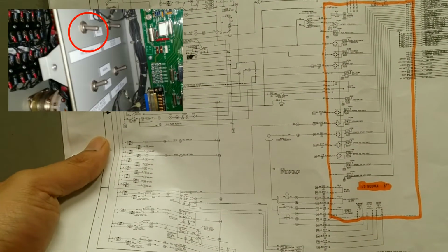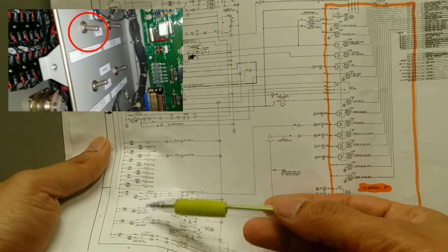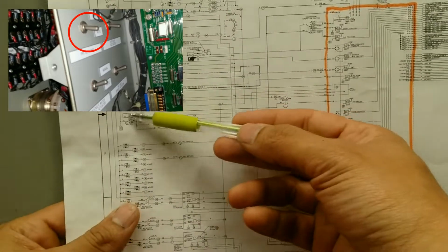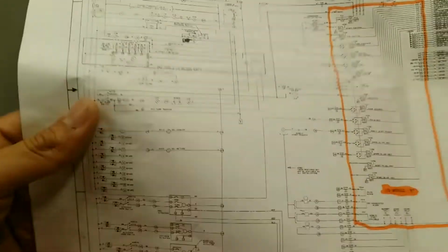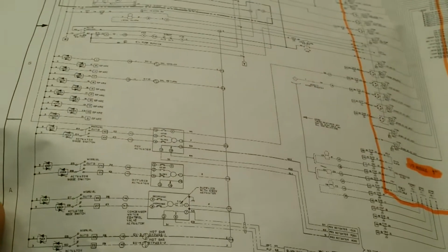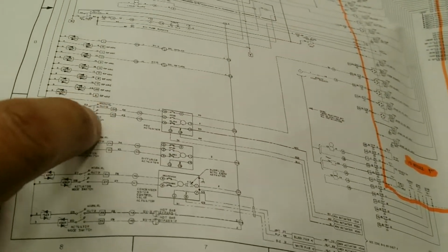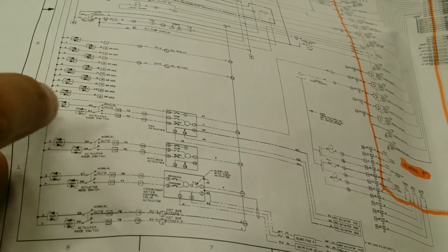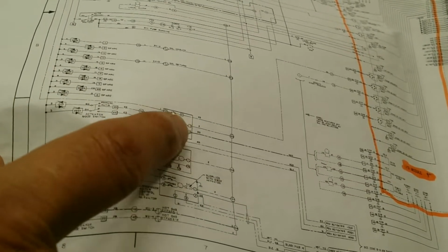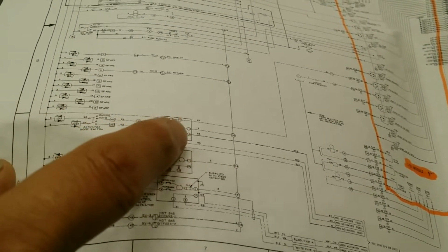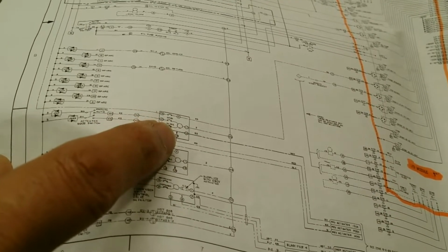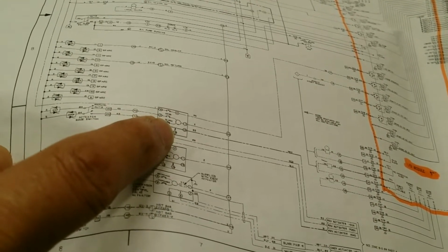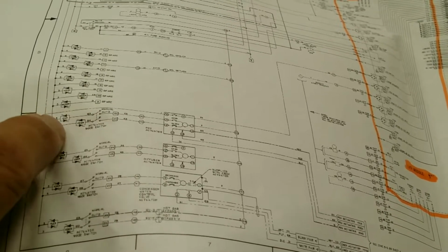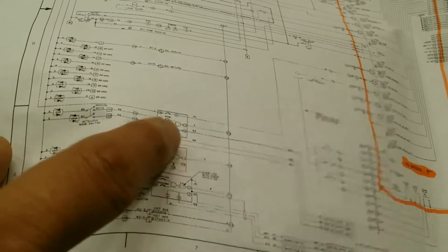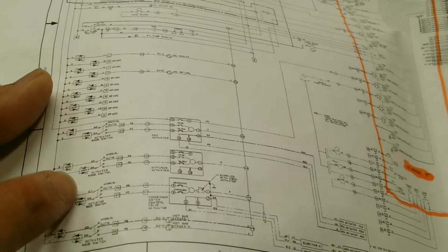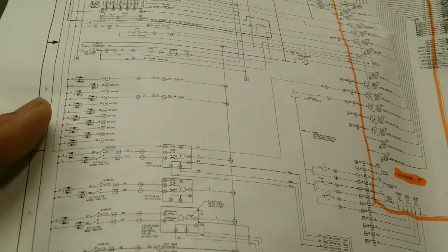Now the disconnect switches, there's 5 of them: 1, 2, 3, 4, and 5. On the bottom 4, I call them disconnect switches because really, if you put it in manual, you are disconnecting the SSRs from the valve in this case, and you can actually go manually, physically open or close the valve. If you put it in auto, now you put the SSRs in line with it. And the same is true for all the other 4 over here.